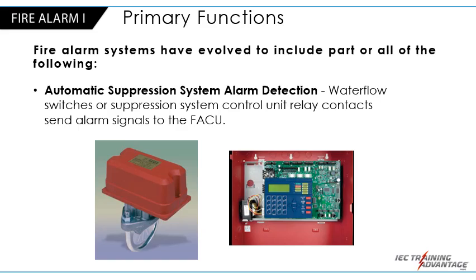Automatic suppression system alarm detection. Water flow switches or suppression system control unit relay contacts send alarm signals to the FACU. Water flow switches, for example, let's say the sprinkler system is activated and water is spraying out of one of the sprinkler heads or multiple sprinkler heads. Well, that will force water to flow through the main sprinkler system. That flow of water will pass through a flow switch, and that flow switch will monitor if there's a flow of water or not. And if there is a flow of water, it will alert the FACU that the sprinkler system has been engaged. This will tell the FACU to notify first responders.